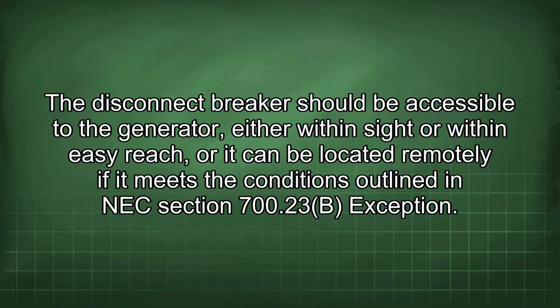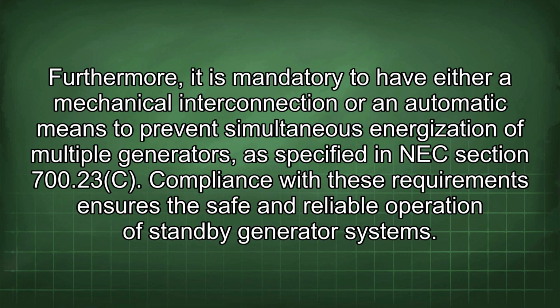The disconnect breaker should be accessible to the generator, either within sight or within easy reach, or it can be located remotely if it meets the conditions outlined in NEC Section 700.23b exception. Furthermore, it is mandatory to have either a mechanical interconnection or an automatic means to prevent simultaneous energization of multiple generators, as specified in NEC section 700.23c. Compliance with these requirements ensures the safe and reliable operation of standby generator systems.